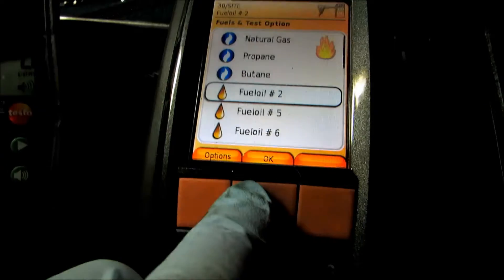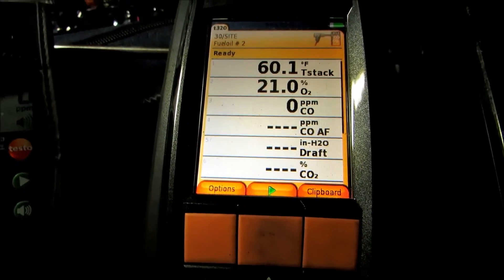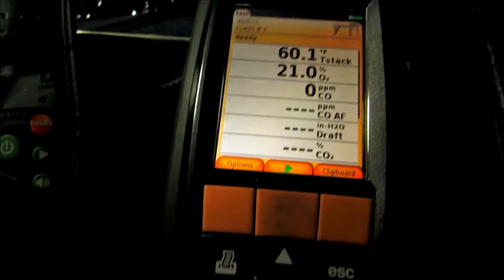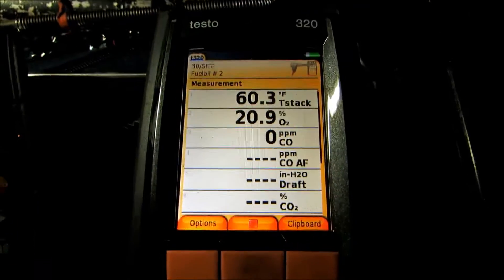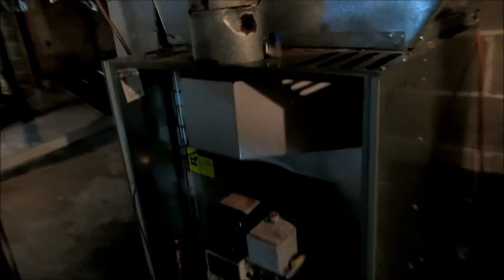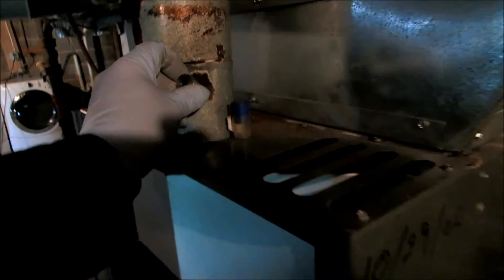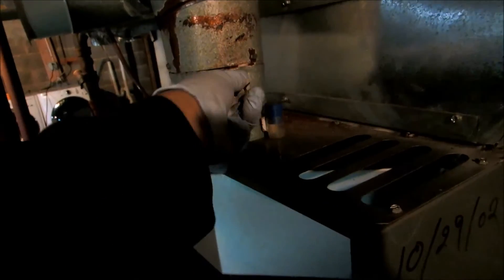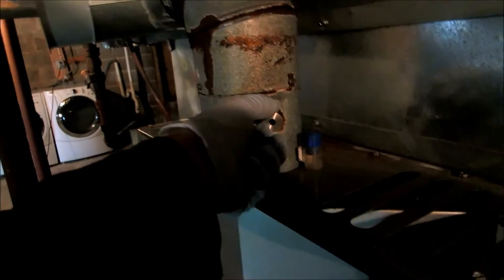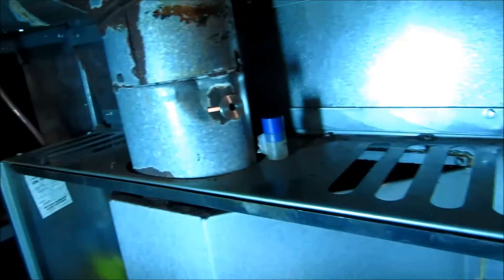Fuel oil number two, it's good. Alright, we'll start it up. Now I like to start it up first because you can get kind of a high reading on the CO when you first start it, so there's no sense in shocking my meter. I'll let it run a little bit and I'll put my meter in there. That's how I like to do it.